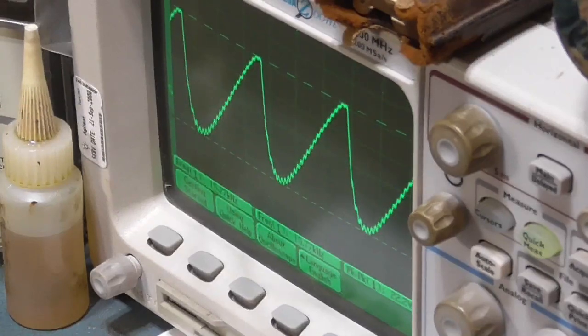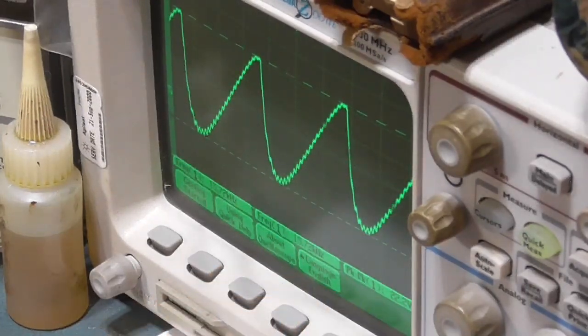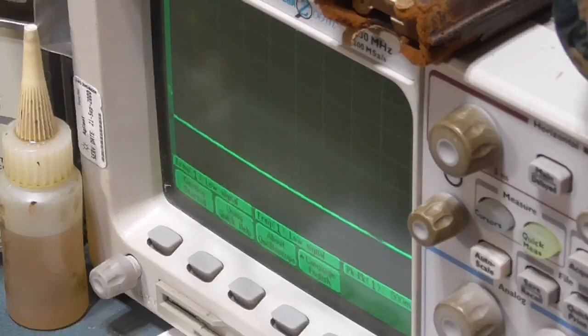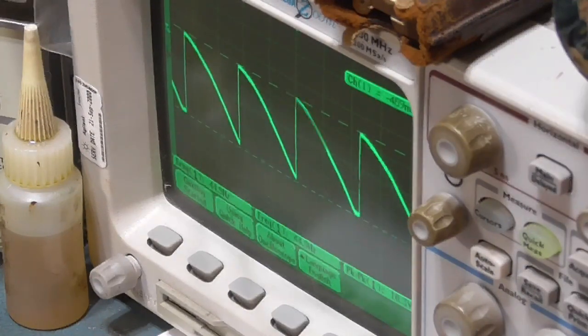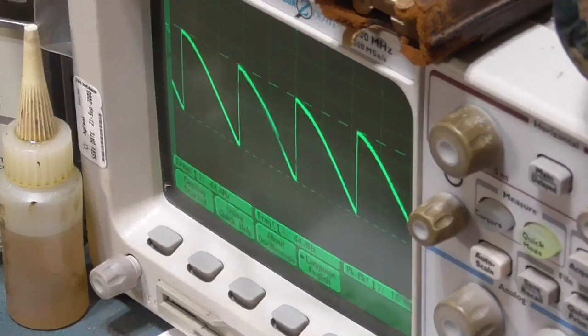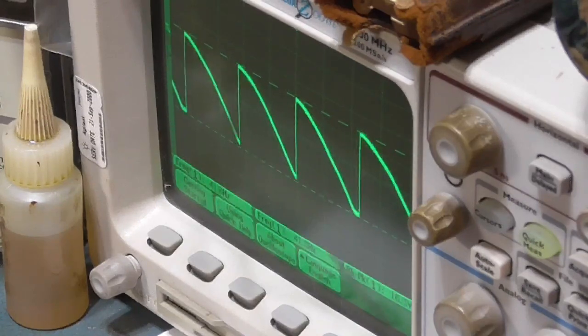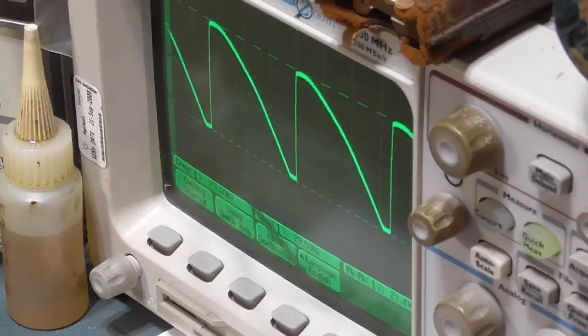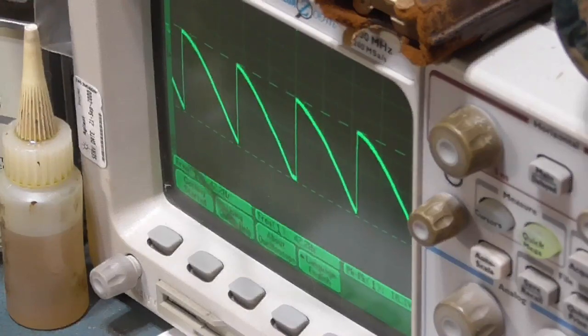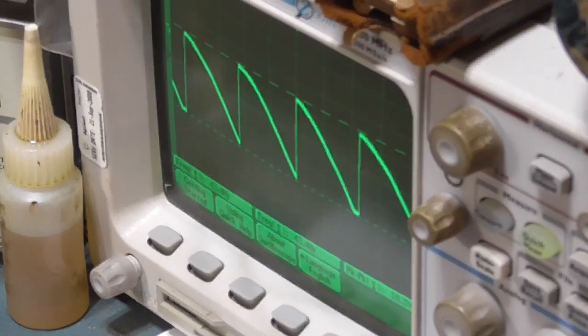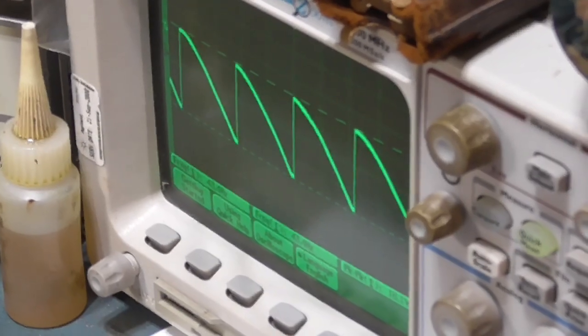Okay, see that's our horizontal. It's reading 15,750. And then our vertical, we're reading 43, and that's all it'll do. It'll go lower, but we can't get higher. We got to get up to 60. Okay, so we've got a capacitor in here that's wrong, or a resistor, one or the other.